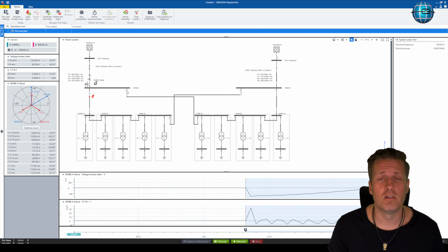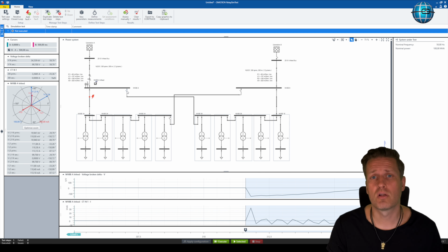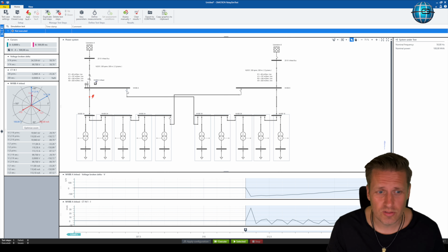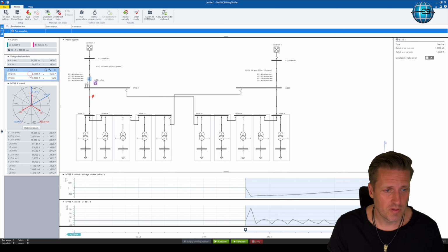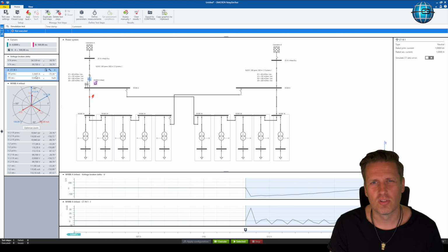Because usually if we put more cables to the grid, the capacitive ground current should increase. So what's going to happen if I close this switch? Will this amount of 3.2 or 6 amps increase or decrease, or will there be no change? Who's able to answer this question?